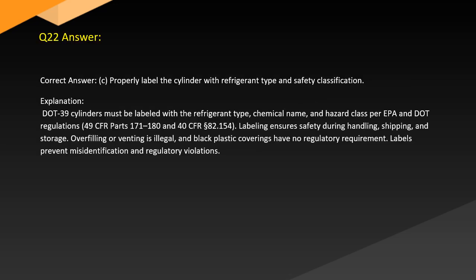Answer. Correct answer, C. Properly label the cylinder with refrigerant type and safety classification. Explanation. DOT 39 cylinders must be labeled with the refrigerant type, chemical name, and hazard class per EPA and DOT regulations, 49 CFR Parts 171, 180 and 40 CFR 82.154. Labeling ensures safety during handling, shipping, and storage. Overfilling or venting is illegal, and black plastic coverings have no regulatory requirement. Labels prevent misidentification and regulatory violations.